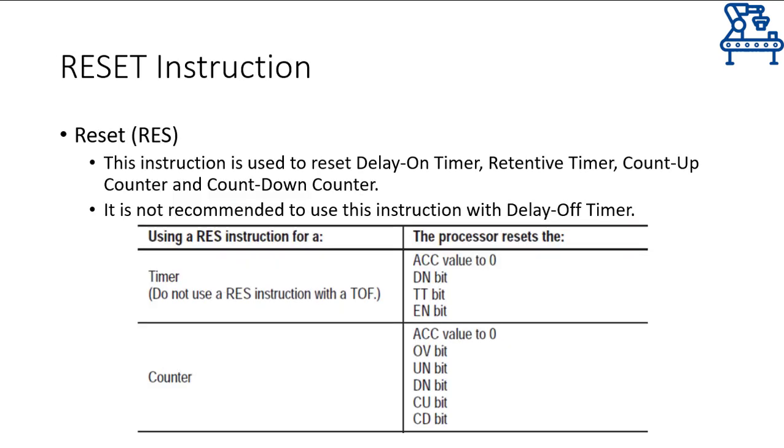The reset instruction may be used with on delay timers or retentive timers to reset them whenever certain conditions are met. Moreover, the same reset instruction is used to reset counters as well, which we will see in a bit. The reset instruction's address will tell it which timer or counter it should reset when its run conditions become true. Now let's move to the simulator to see the timers in action and see how a reset instruction works.